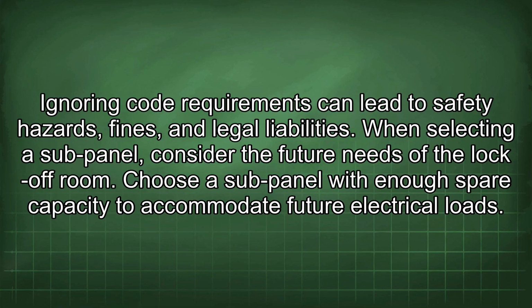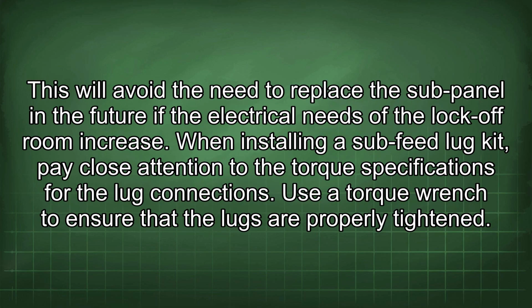When selecting a sub-panel, consider the future needs of the lock-off room. Choose a sub-panel with enough spare capacity to accommodate future electrical loads. This will avoid the need to replace the sub-panel in the future if the electrical needs of the lock-off room increase. When installing a sub-feed lug kit, pay close attention to the torque specifications for the lug connections.